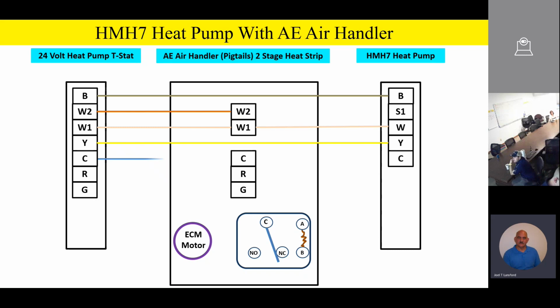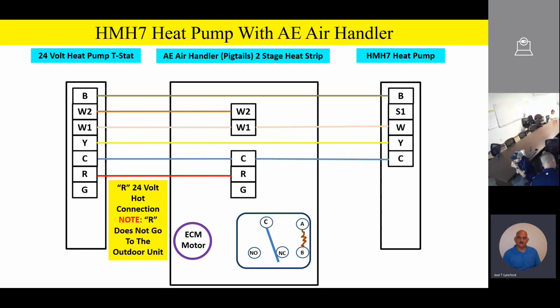C terminal is 24-volt common. It goes from the thermostat to the outdoor unit and to the indoor unit. Goes all the way through. The R terminal is 24-volt hot from the thermostat to the indoor unit. Now, please remember, team, this does not go outside. Unlike our other products where we have an R terminal outside powering up the control outside, we don't need that with the HMH7. It's just strictly 24-volt hot from the thermostat to the indoor unit.